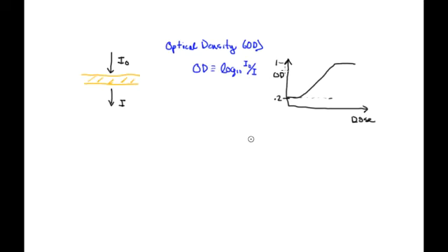So it might saturate at an OD of 1. That saturation depends on the speed of the film and so on. Oh, by the way, you plot the logarithm of dose here usually. And so this is the very typical curve. It's called the H&D curve. That's for Hurter and Driffield, who characterized this in the late 1800s.